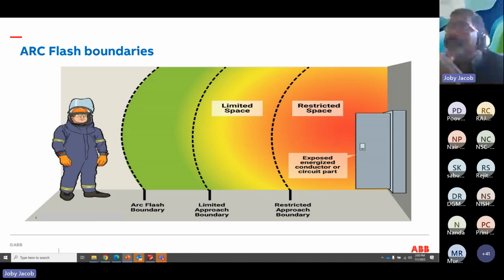That's the area where you can still have an arc flash injury, because the arc flash can travel depending upon the following parameters we have discussed. Still you are vulnerable to that arc flash. You can get a burn injury more than second degree burn. And when you calculate the area where you stand, the arc flash boundary, that's the area where it's safe, where the maximum incident energy can be less than a second degree burn, actually. So even if you get splinters or anything, you are safe, and you are at a safe distance, basically.